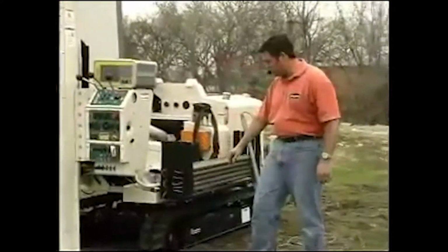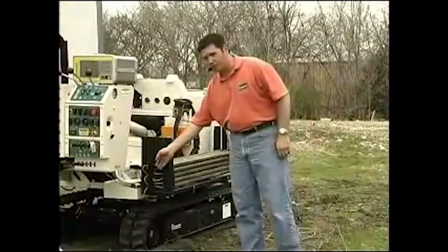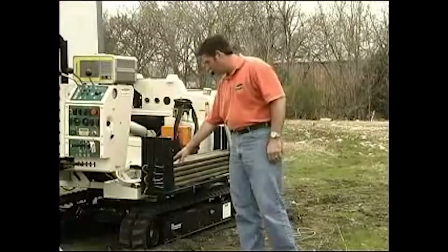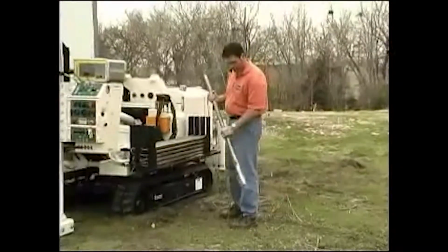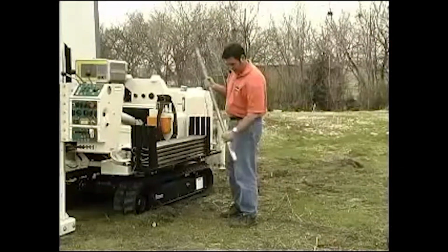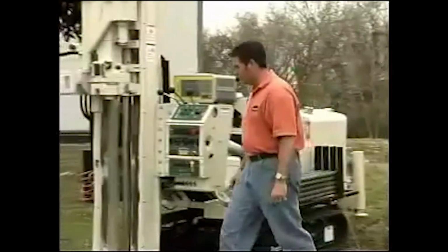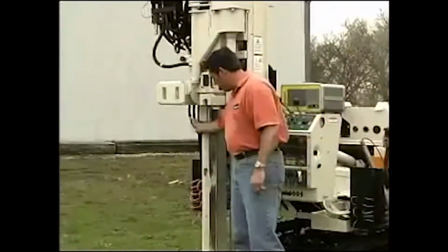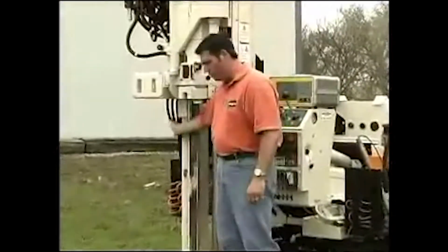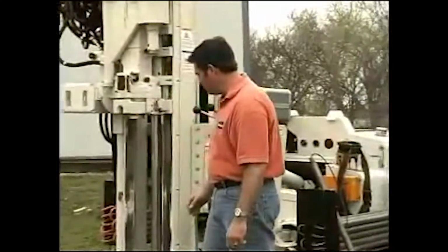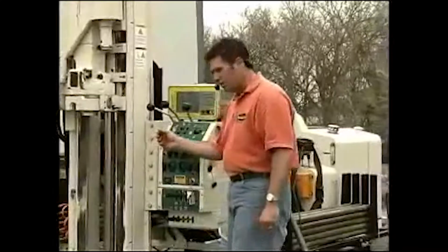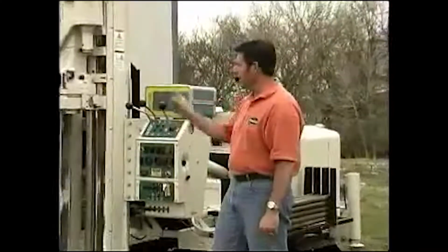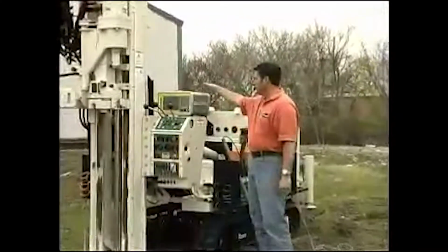I've got my rods pre-strung, so you can see my conductivity cord is running through the ID of my rods. I've got my conductivity probe connected. I'm using the SC500 with my connecting rod. Located on the other side is my string pot. Once again, same principle as all of our downhole tools, we have to have a method of measuring depth. That's mounted up on the bracket and a cord running from it through the hose reel to the back of the field instrument.